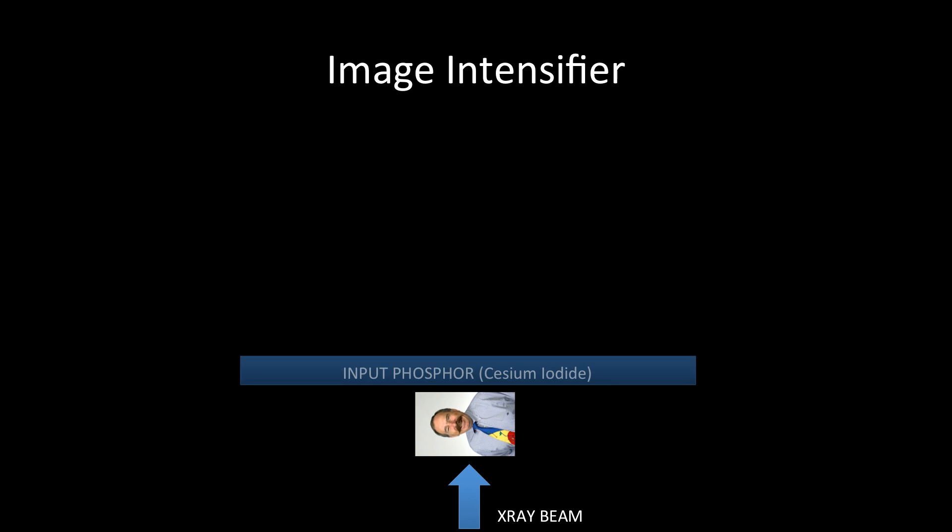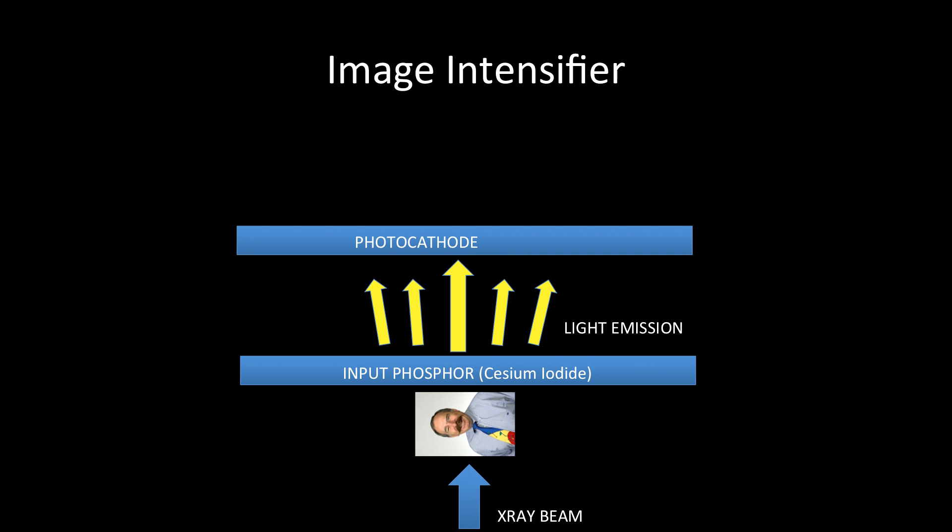Then we have the first layer of the image intensifier tube, and that's the input phosphor. It is made of cesium iodide. This generates light photons. Then the light photons will hit the photocathode. At the photocathode we have the photoelectric effect, and this means we will convert the light photons to electrons. Remember, x-rays are still photons, so we went from an x-ray photon to a light photon, and then we converted that light photon to an electron by means of the photocathode.